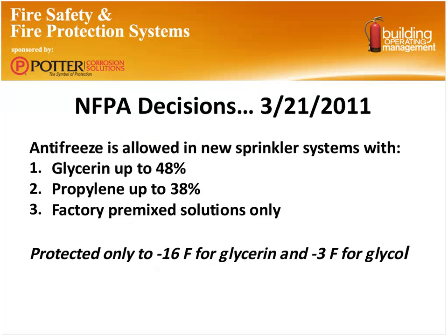Those of us in the northern climates, what we've run into is that in some cases that's not sufficient freeze protection. And the reason for that is those concentrations really only get you down to a -16 if you're using glycerin, and a -3 degrees Fahrenheit if using glycol.